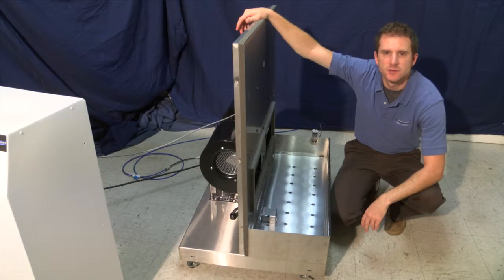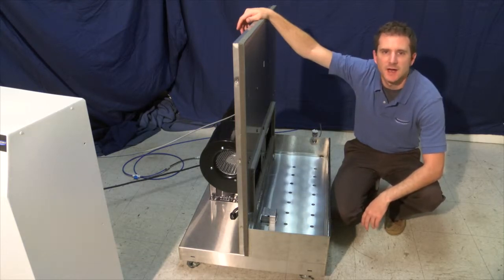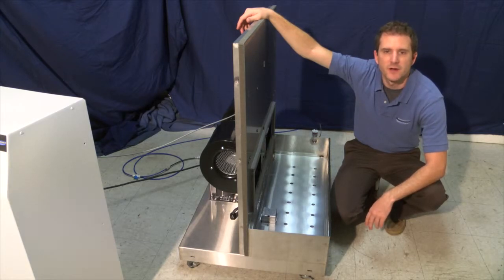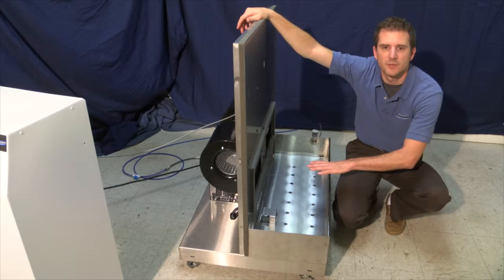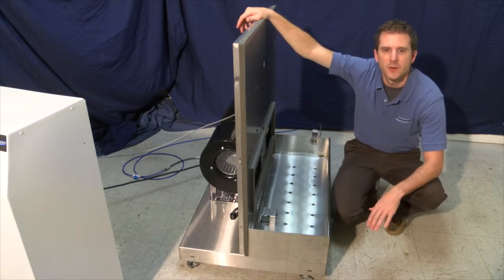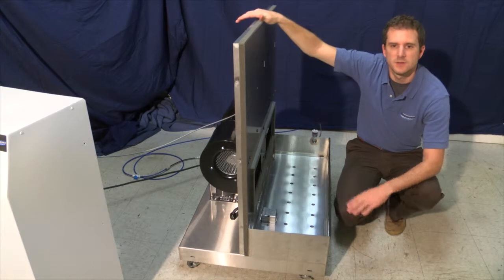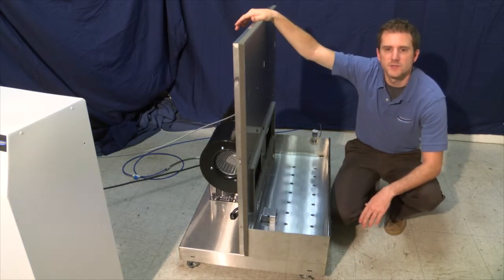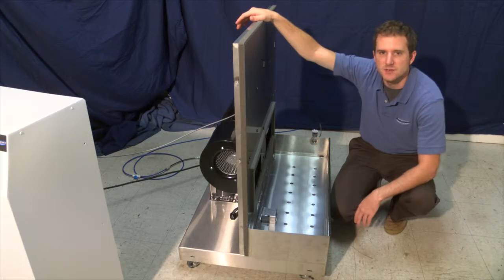The most common troubleshooting scenario is the unit's transducers not operating, or the unit does not produce mist vapor. If you hear your humidifier running, but the relative humidity in your space is not increasing, this may mean your transducers are not operating. The easiest way to verify the transducers is to visually inspect the water pan while the unit is operating. Turn your unit off and remove the fan cover and chute to get at the water pan. Restart the unit and make sure the set point on your humidistat is higher than the relative humidity reading. We will now show you operating transducers.